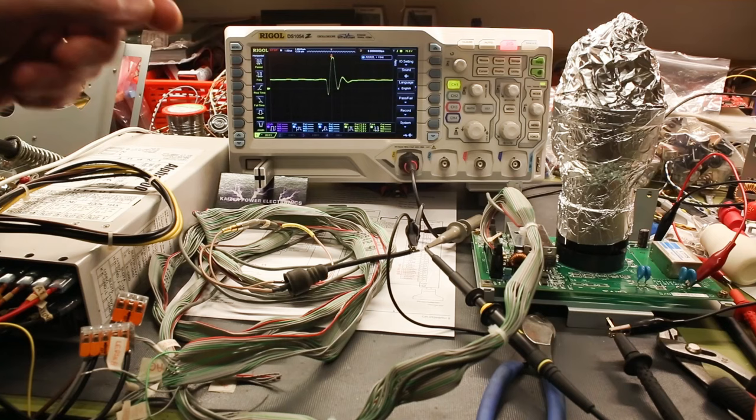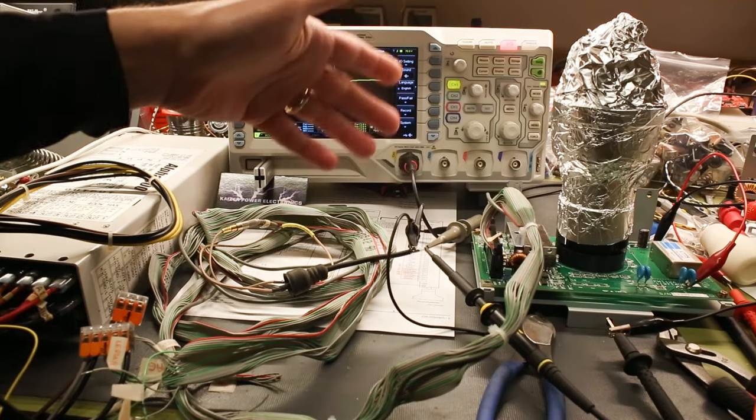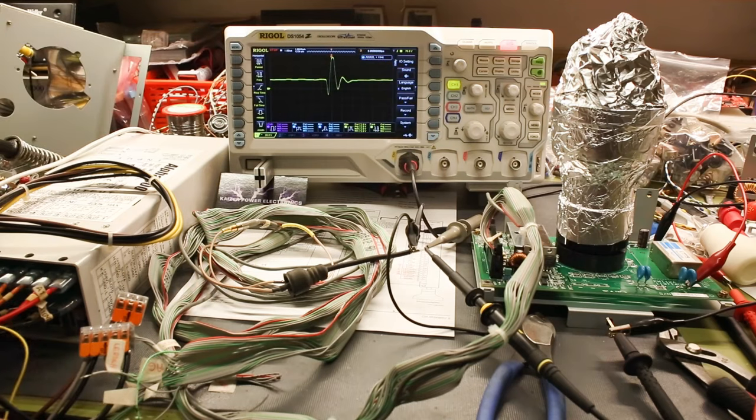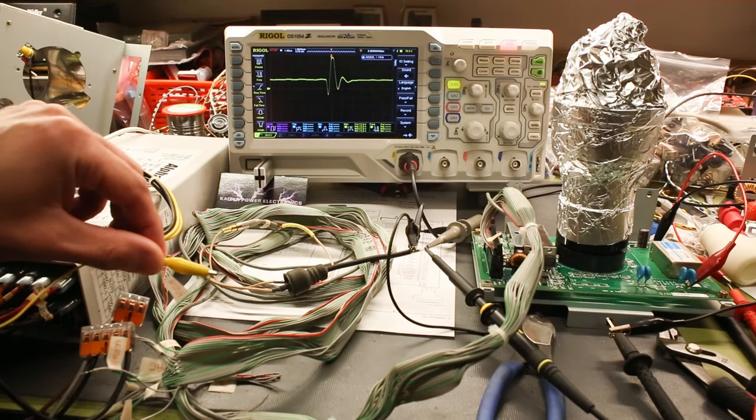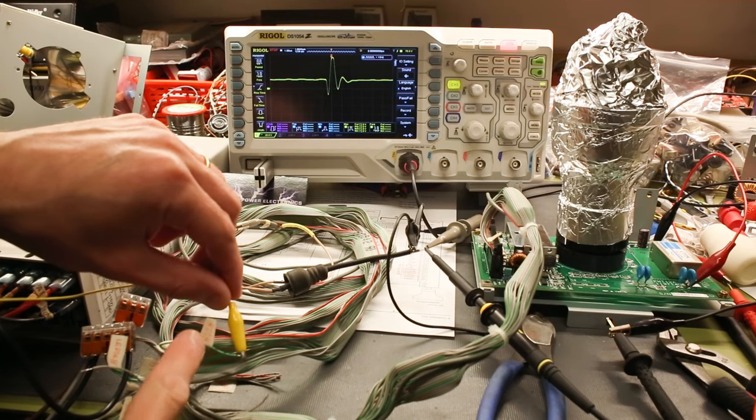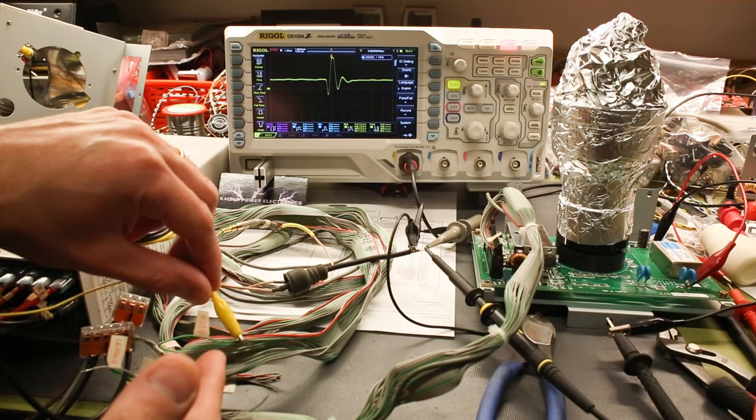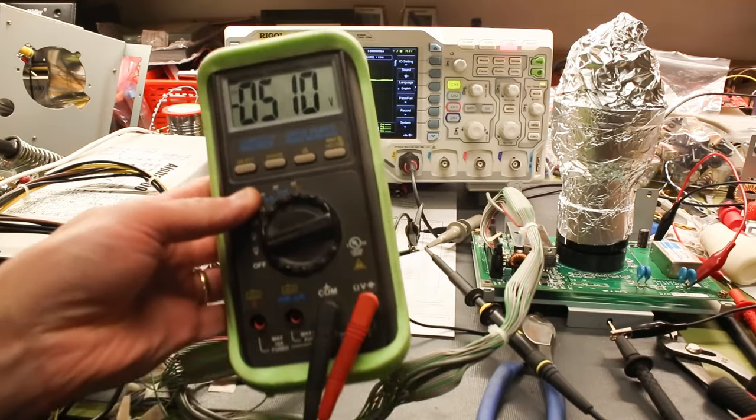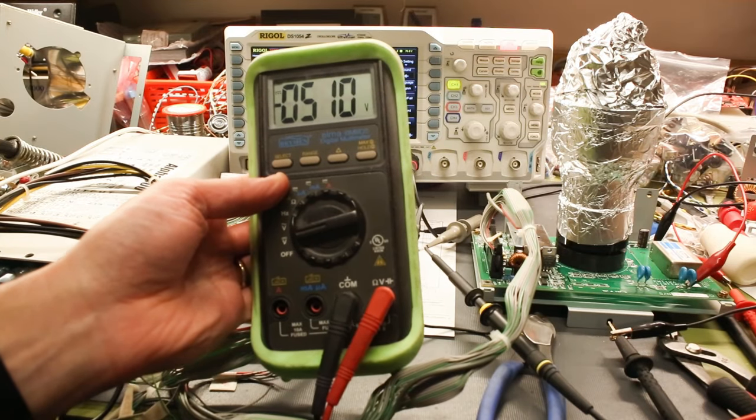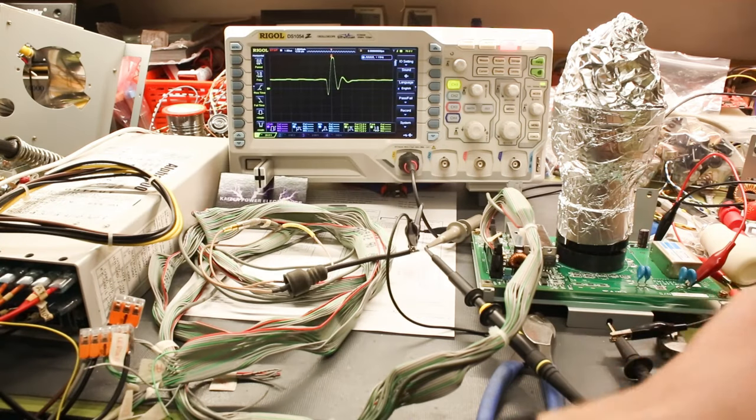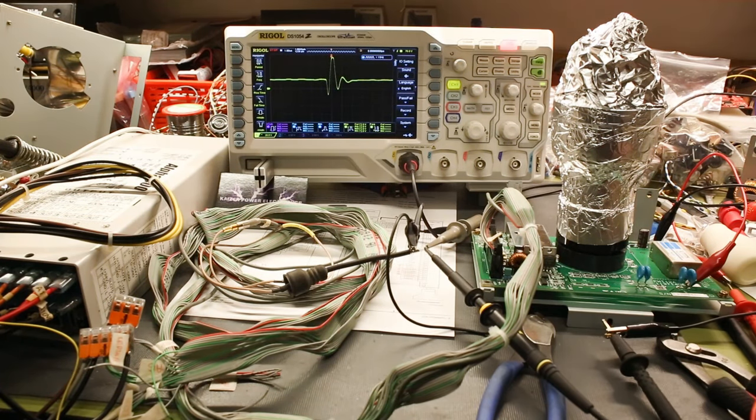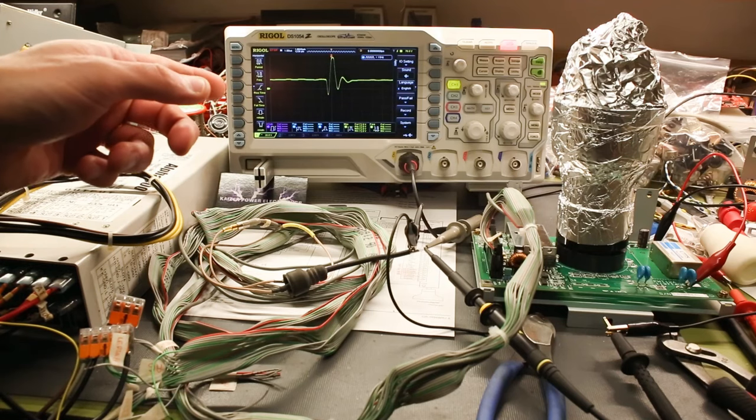Browsing through the manual, I discovered there was a description of this board having a hardware okay and a software okay for the high voltage to run. It has some internal logic for the hardware okay, but the CPU card has this input pin, HV software high, which needs to be pulled to plus 5 volts to activate the negative high voltage supply. As we can see, it's running at minus 510 volts. This is a tad low for particle detection but sufficient for x-ray image scanning.